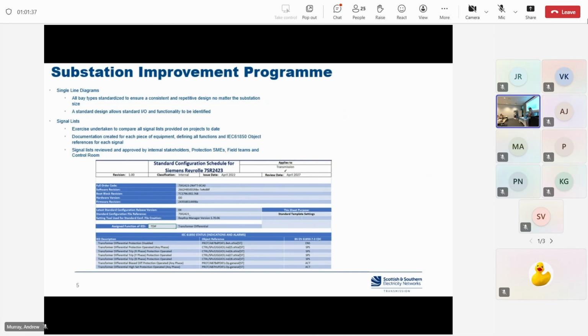That was a very important step because when we delivered the first four sites, what we found initially was the protection engineers who were doing the engineering on the relay were fine with the description. When we got those signals to site, the field engineers commissioning those signals were not happy with the descriptions. So to standardize the signal lists, we had to get everyone's buy-in from the outset. That included the control room again, because once we had the field teams' buy-in and they were commissioning the signal, the control room would then see the signal list and would not be happy about something on the list. So you have to get all these different stakeholders involved as early as you can to make sure there's agreement and it stops unexpected changes coming further down the project line.